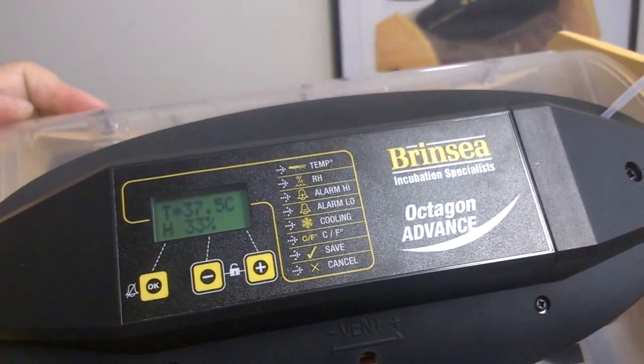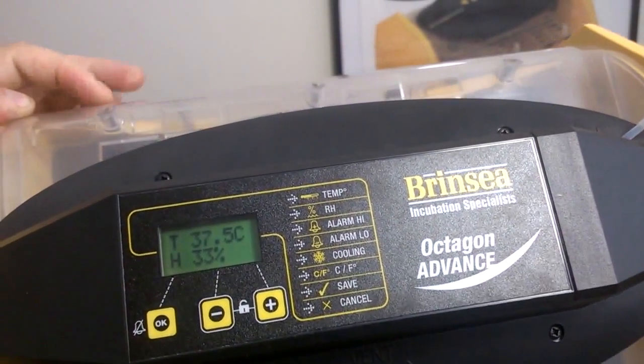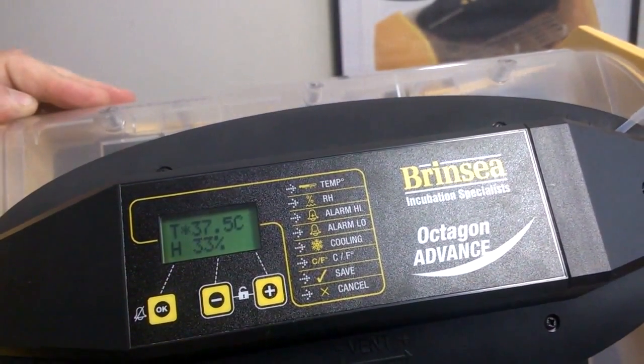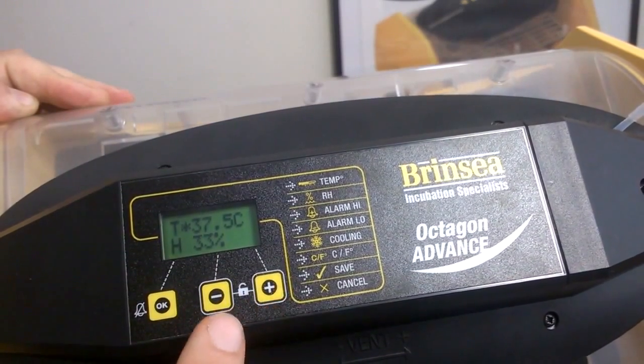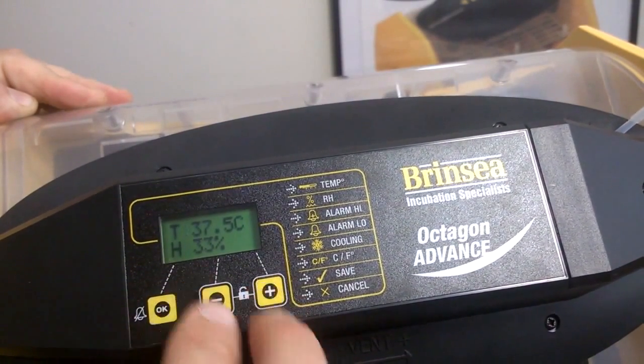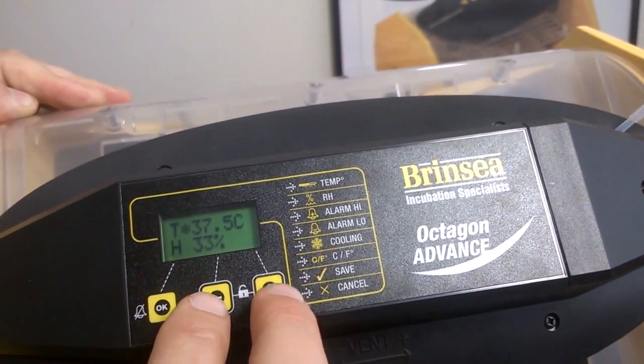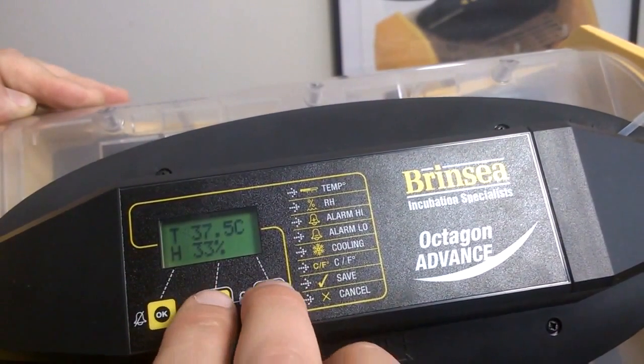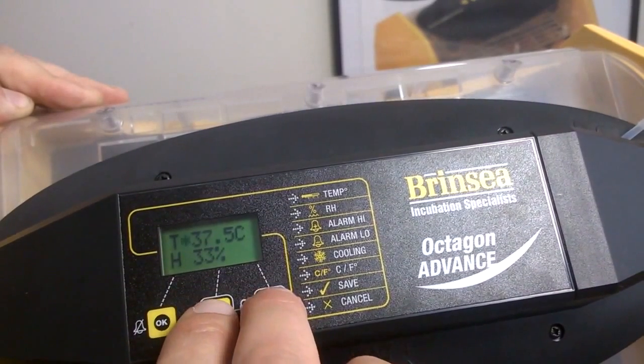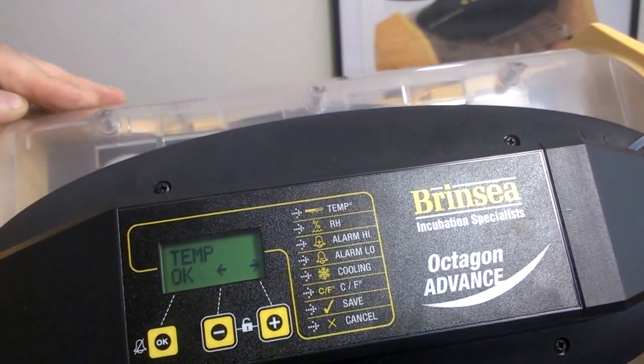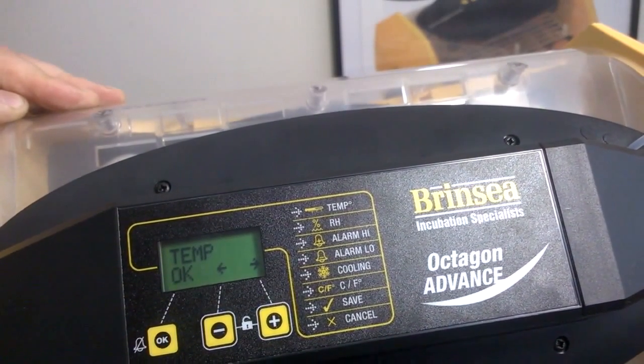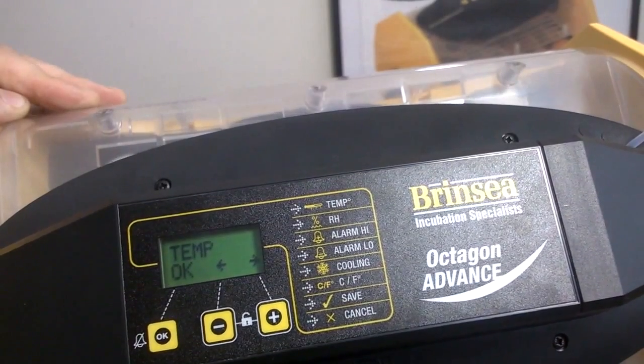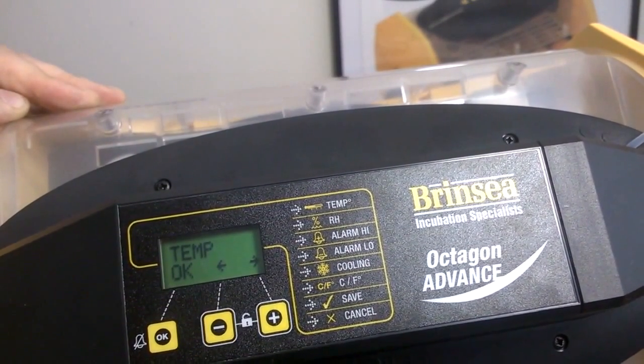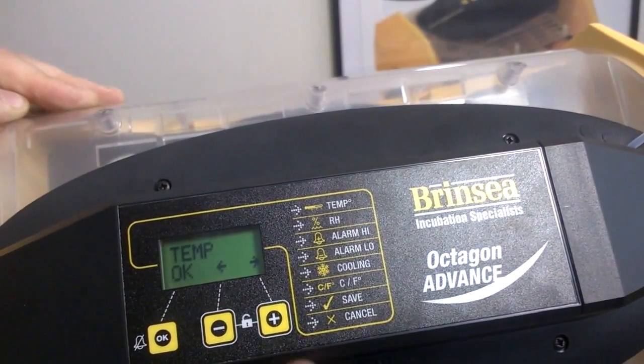So what I've got to do now is go into the menu and change the humidity setting. In order to do that, I need to press the minus and the plus key down together. If you don't get them down together, it won't take you in, so sometimes it takes a little bit of fiddling to get in, but it is fine. Let's have a go. There we are. It's taken me straight in to the first setting by unlocking the menu. I go straight into temperature, and that is the temperature setting. If I wanted to change things around the temperature, I would OK that, but I don't. I want to move on to humidity because that's the one I'm interested in.